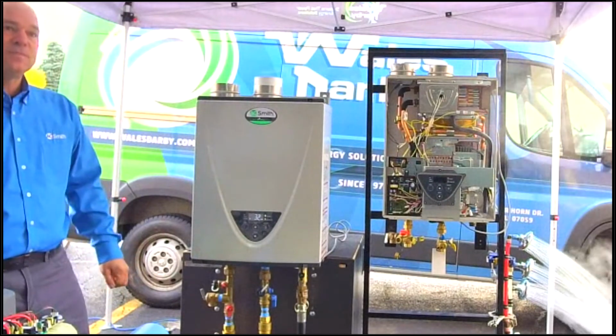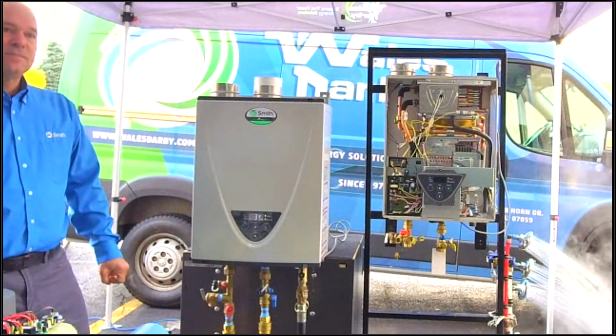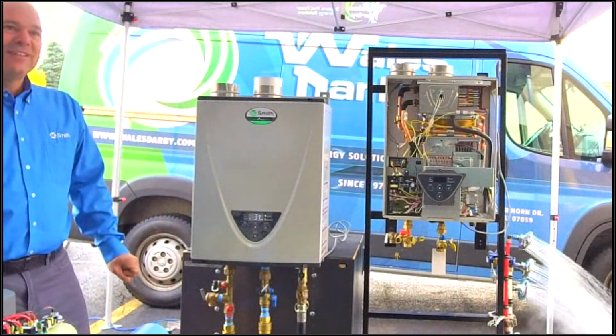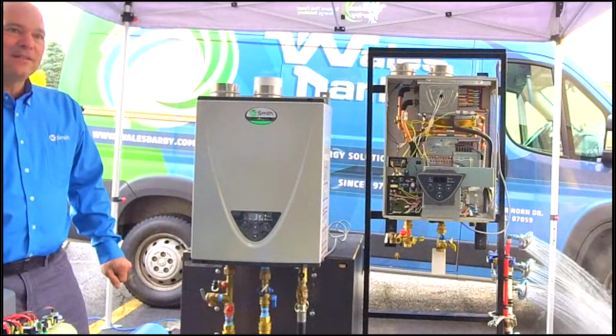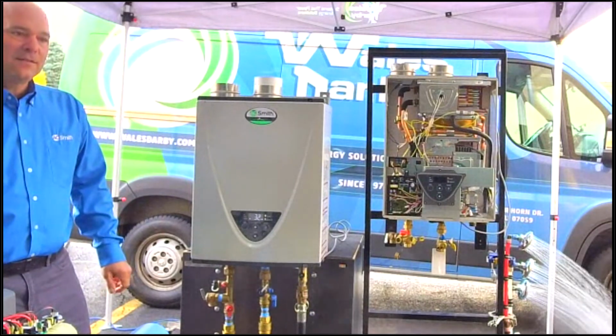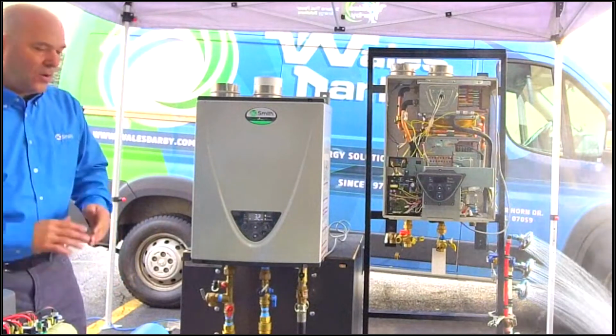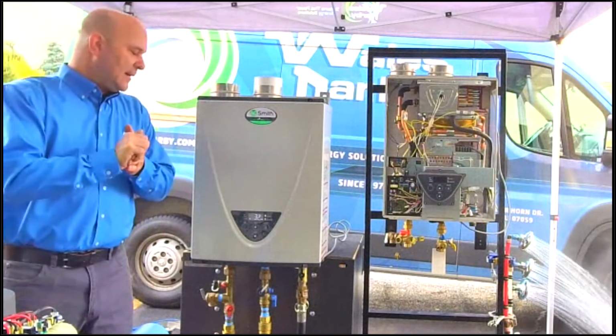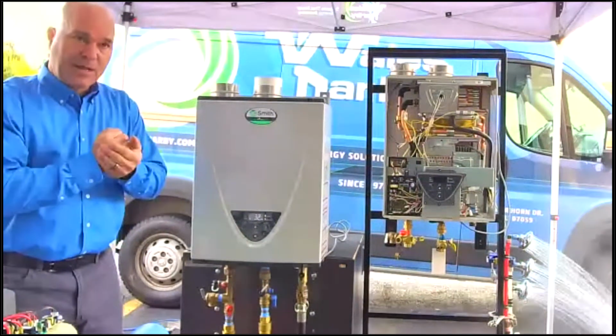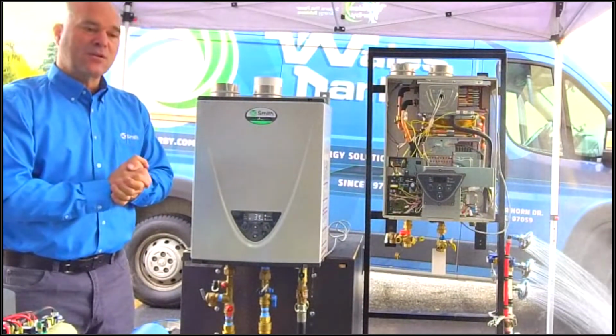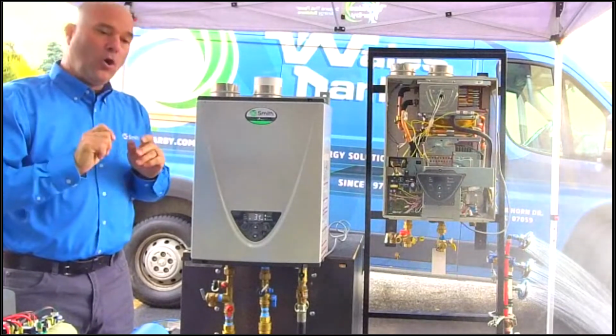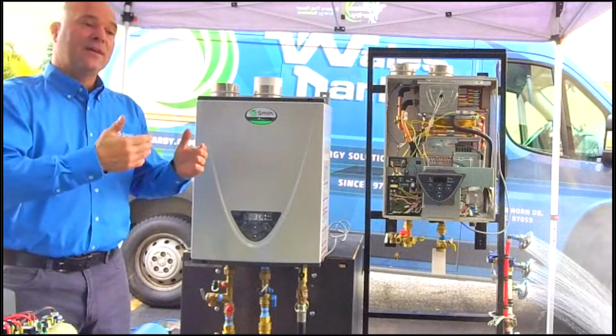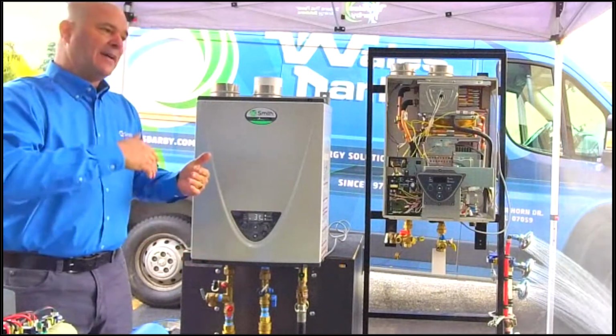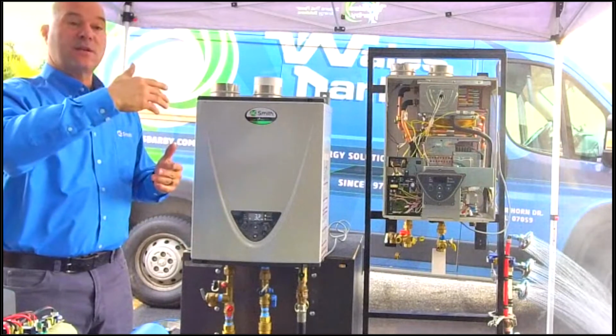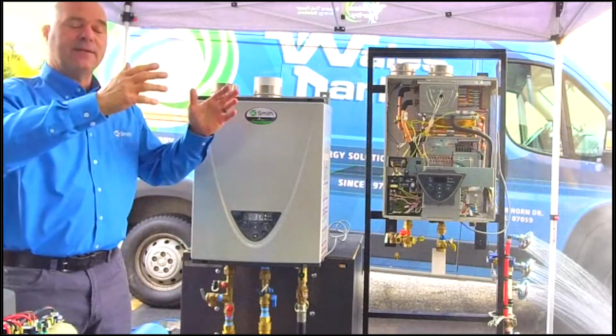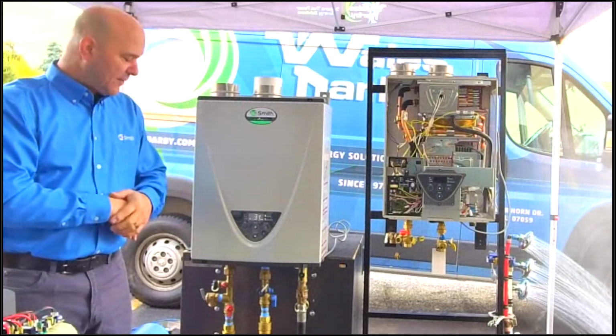What else you got for questions? All right, so I actually got 2 questions that are relatively similar. One is, can this unit be piped in primary, secondary, and used as a hot water boiler? And the other one is, can it be used as a combi? Okay, so we do not have an H stamp on this unit. We do see them used quite a bit as a combi. The goal, if you use this as a combi, you would have to have a stainless steel circulator. You would have to be hooked to a device that is a potable device. So if you have an air handler, it has to be qualified as a potable water device.